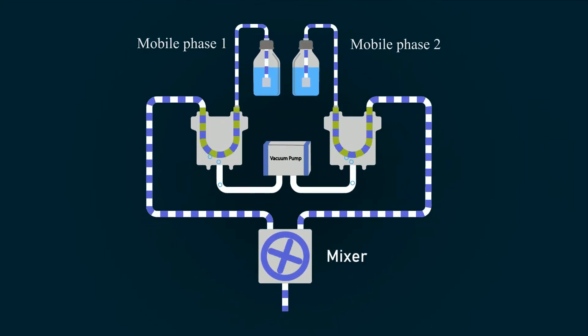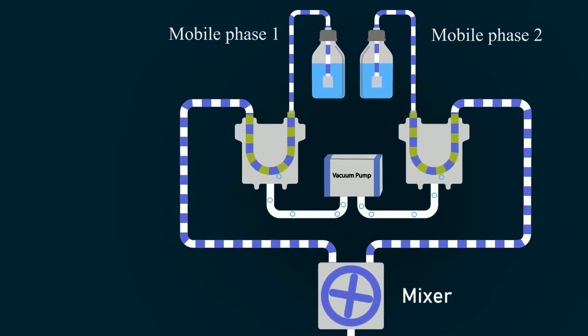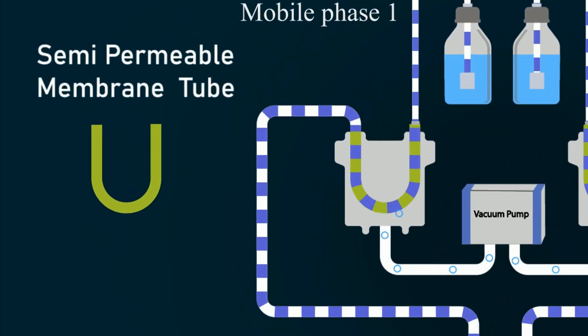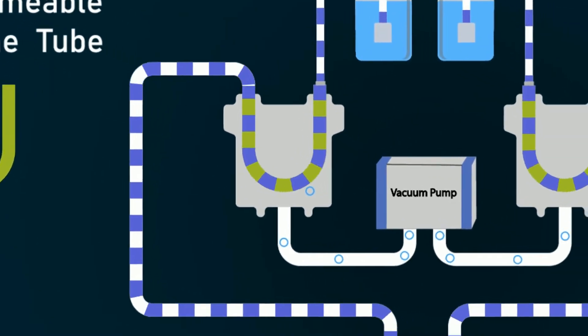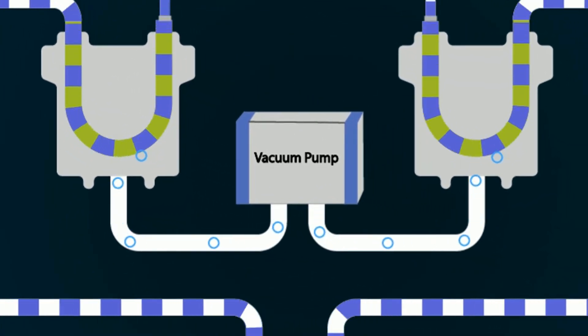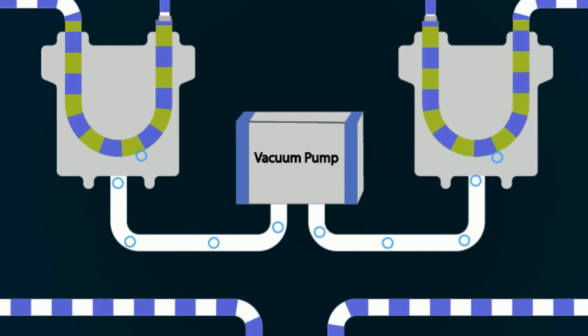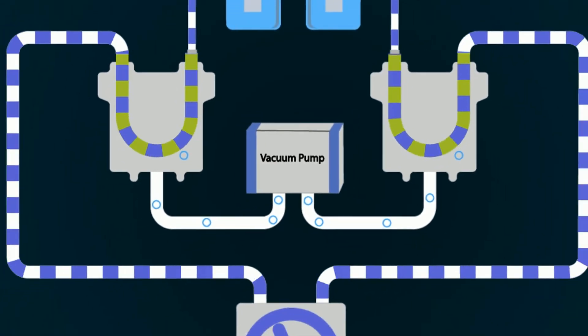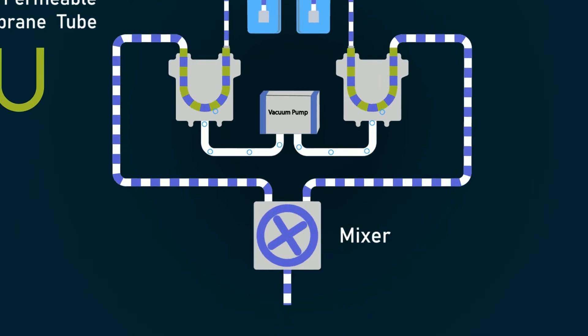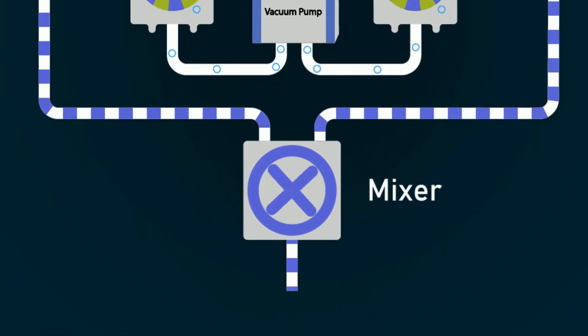The vacuum pump sucks the gas bubbles from the semi-permeable membrane tube. As you can see, all the bubbles are moving from the stream to the vacuum pump. And then the solvents are mixed using the mixer.